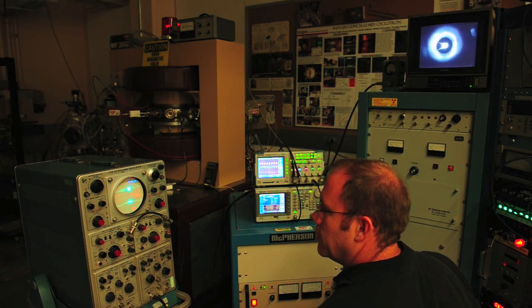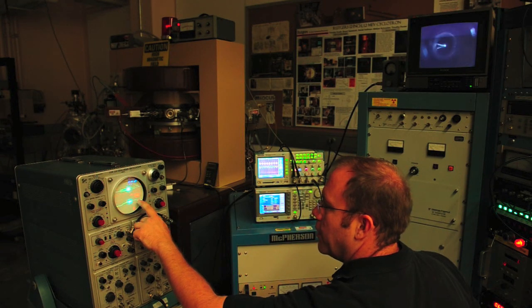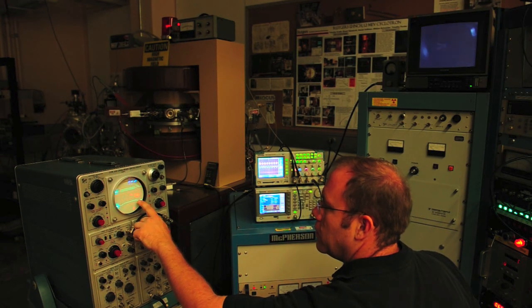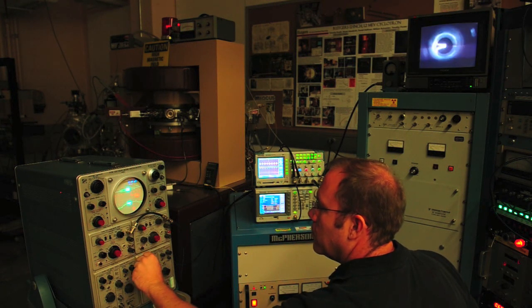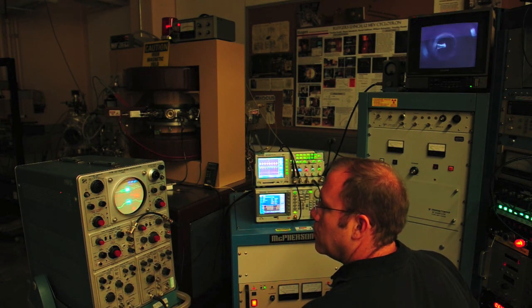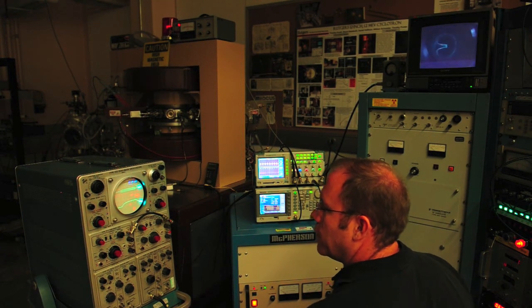So I'm adjusting the magnetic field to optimize the beam current. I'm going to tune for peak beam current on the Faraday collector. So I've gone through the peak, and I'm coming back. And that's optimized.